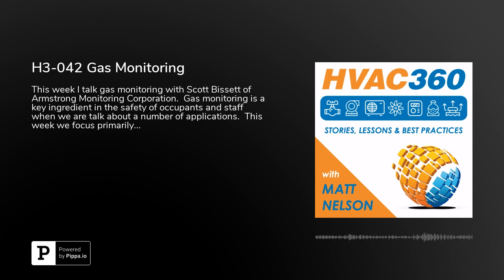Now, what about one of my examples, the chiller entrances, at the entrance to a mechanical room? What are some of the things that you'd expect to see? Audible alarm, a visual alarm, possibly a manual shutdown. Yeah, by code, we need to have audio and visual alarm. Not at every entrance, but likely at the main entrance to the mechanical room. You do need a shutdown for combustion sources, and you do need ventilation interlocks. So you need the ability to turn on exhaust fans in that space from outside of the room.